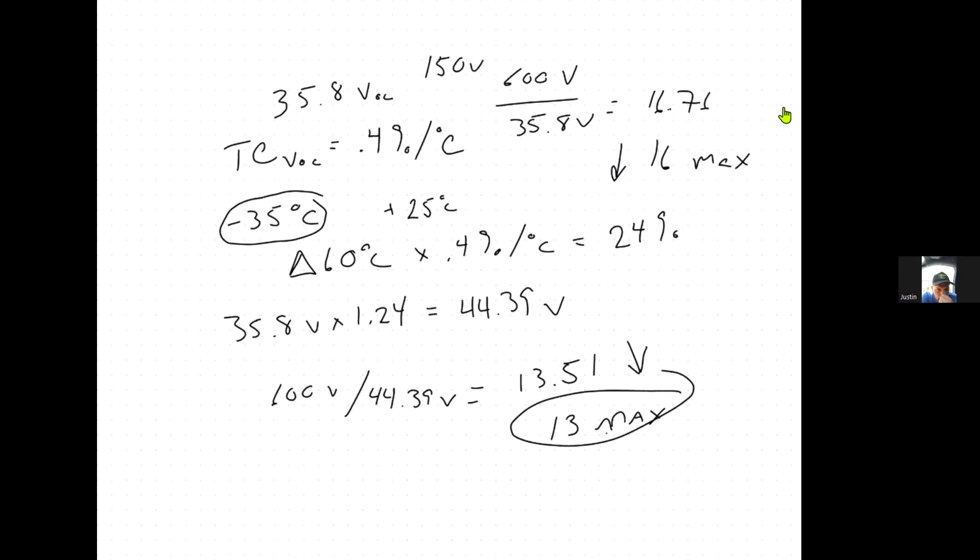It might be 150 volts, it might be 100 volts, it might be 80 volts, whatever. And I just say, on the hottest day ever, what's the minimum amount of voltage I can get that will start my inverter? Because if I have too few panels in the string, on a hot day, it might be exactly the same as nighttime. That inverter never kicks on because it never receives enough voltage. So you need to know the minimum. Very common in today's world, you're going to be dealing with a number around 11, 12, 13 max and 4, 5, 6 somewhere in there minimum. So your numbers are going to be somewhere between, say, 6 and 13 for the size of the string for a grid tied system, string inverter.